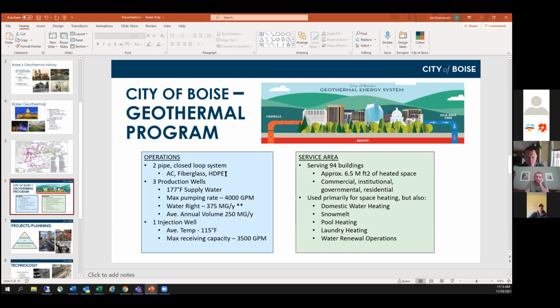There are some downsides with HDPE, or with all plastic pipes, and that's the coefficient of thermal expansion and contraction. We're monitoring that closely to make sure that as this pipe heats up and cools down, as buildings cycle on and off, the thermal expansion and contraction isn't pulling away from any valves or from buildings or any parts of our system.